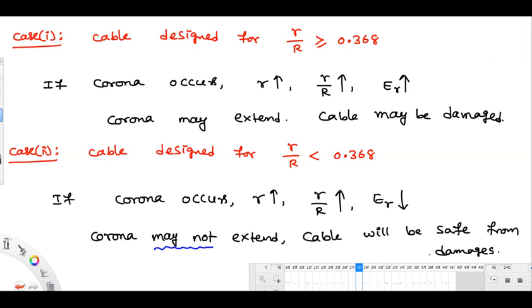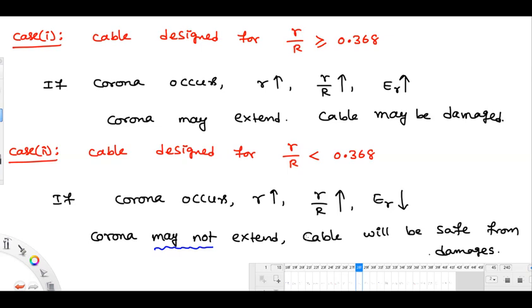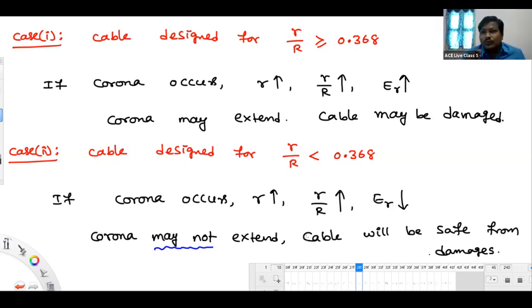Because in the transmission line, the virtual capacitor actually provides reactive power. I understood your doubt. You are saying that we have a lagging load, and if you connect a cable, will the power factor improve or not. That's your doubt, right? Yes. Load power factor will not change. Your source power factor will improve.